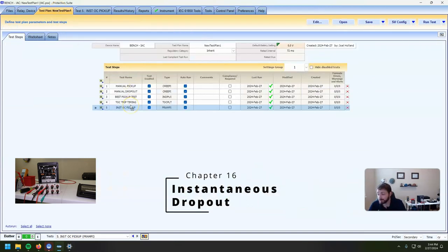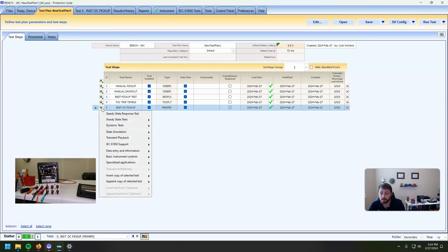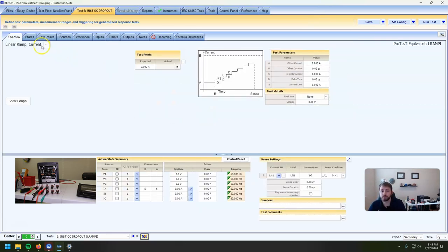So that's our instantaneous pickup. Now I've got one more that I have to do, and this is a NETA requirement. If you're not testing per NETA requirements, if you're only doing this per the manufacturer's instructions, we can forego this one, but I want to show you what happens and how to do this. We are going to do a linear ramp current — and this is the dropout on the instantaneous unit, the instantaneous OC dropout.